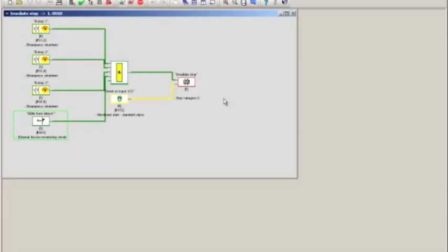OK. On the diagnostic screen, we see that the three e-stops are in fact released and the EDM gives us a true signal. In this case, that doesn't mean that the EDM feedback loop is closed. It means that it's in the right proper state, which happens to be closed in this case simply because the safe outputs are open.